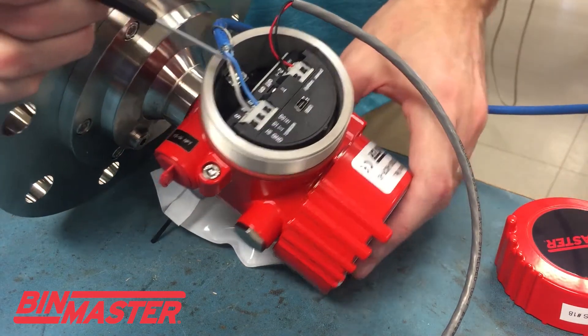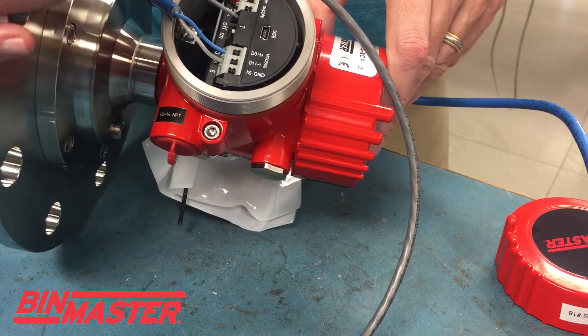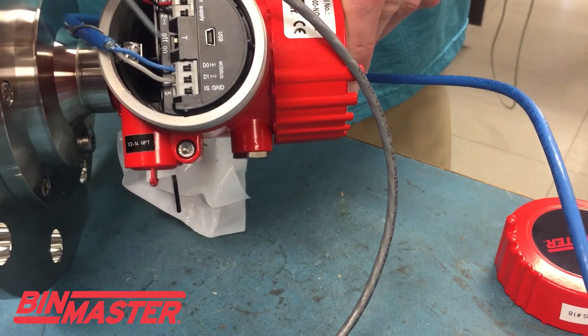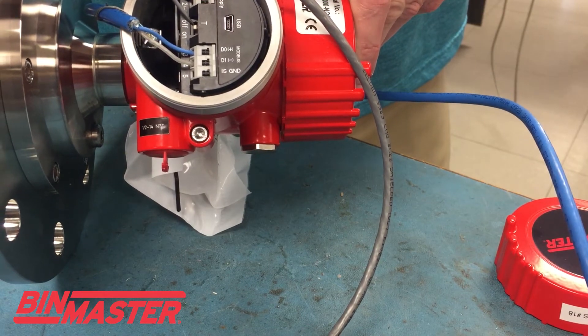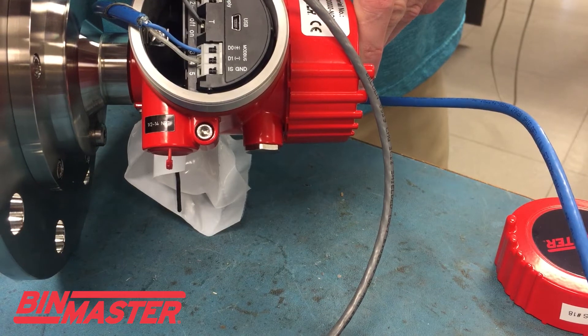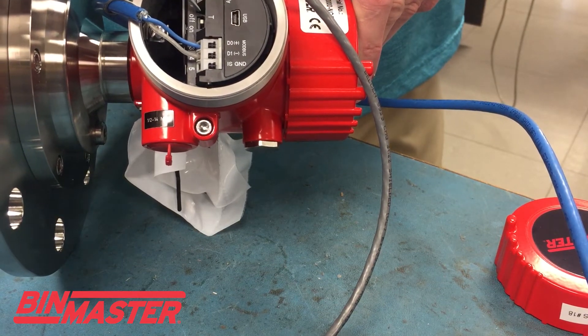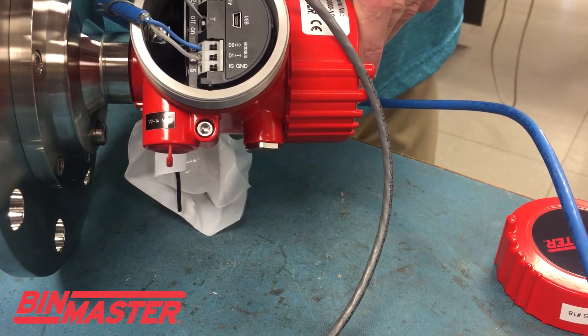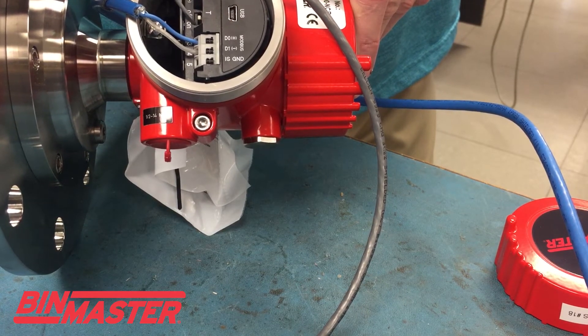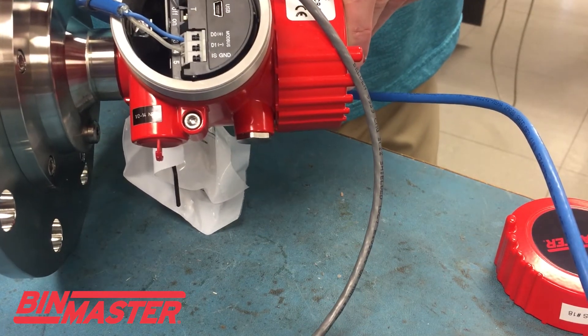There is one thing I'll mention — a termination switch that a lot of customers really don't seem to know about in my experience. This termination switch, by default, is set to off, just like with our SmartBobs. The very last radar, if we have multiple units in a daisy chain, or even just one if it's at the end of the daisy chain, this termination jumper should be switched from off to on like I've done here.